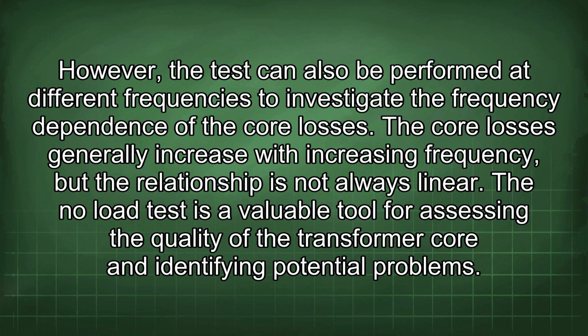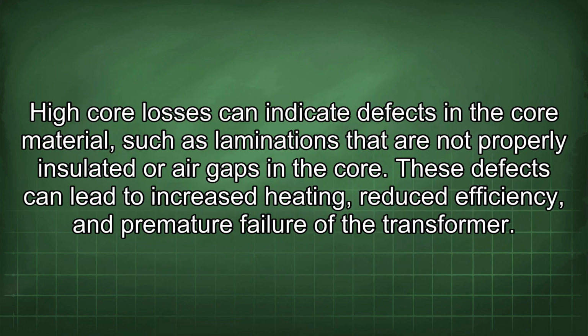The no-load test is a valuable tool for assessing the quality of the transformer core and identifying potential problems. High core losses can indicate defects in the core material, such as laminations that are not properly insulated or air gaps in the core. These defects can lead to increased heating, reduced efficiency, and premature failure of the transformer.